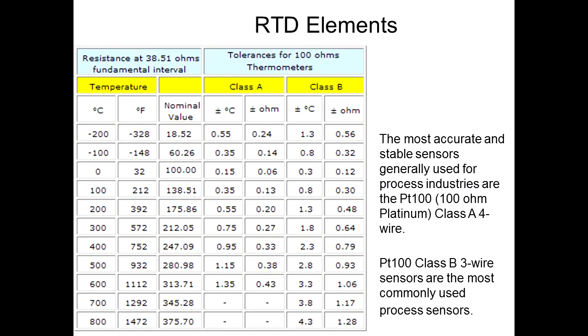So these are some tolerances for RTDs. Class A, you will see, has a resistance level at 0C, which is the platinum, 100 ohm platinum, and it is allowed a 0.06% resistance error at 0C. What that means is a 100 ohm RTD can be 99.94 to 100.06 and still be a Class A.